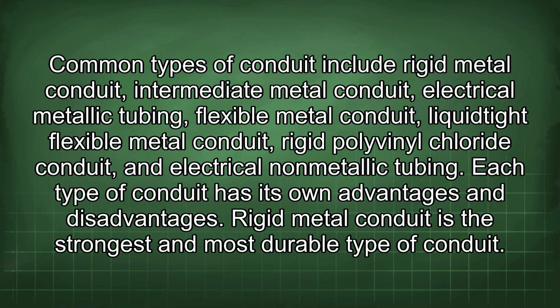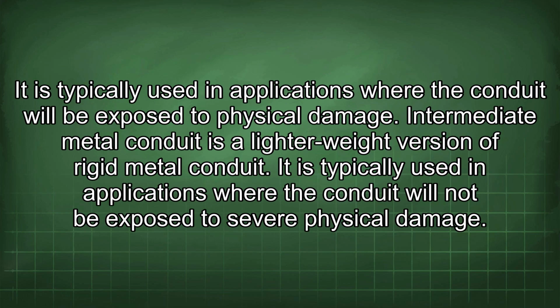Common types of conduit include rigid metal conduit, intermediate metal conduit, electrical metallic tubing, flexible metal conduit, liquidtight flexible metal conduit, rigid polyvinyl chloride conduit, and electrical non-metallic tubing. Each type of conduit has its own advantages and disadvantages. Rigid metal conduit is the strongest and most durable type of conduit. It is typically used in applications where the conduit will be exposed to physical damage. Intermediate metal conduit is a lighter weight version of rigid metal conduit. It is typically used in applications where the conduit will not be exposed to severe physical damage.